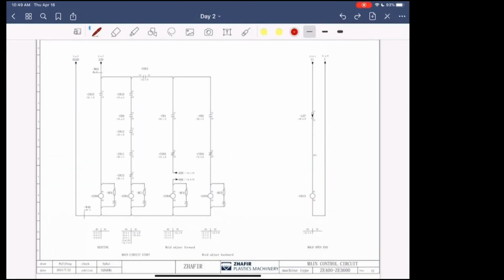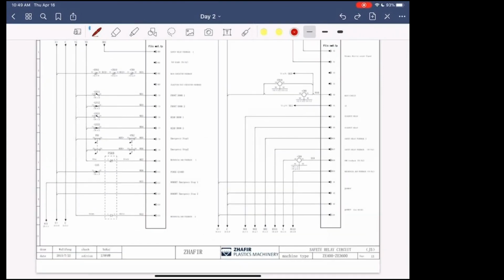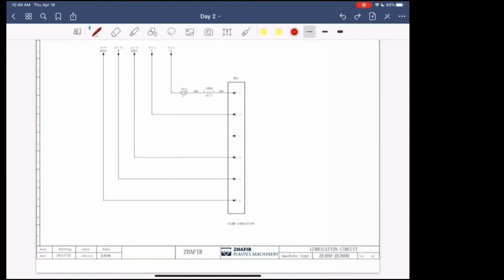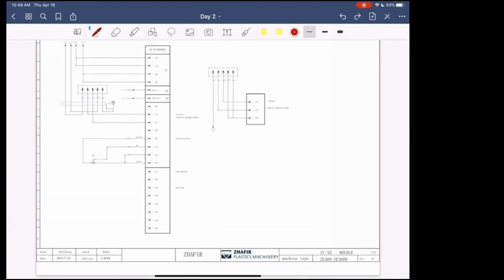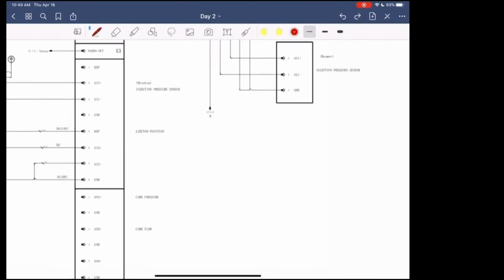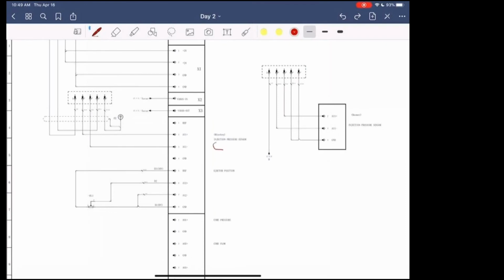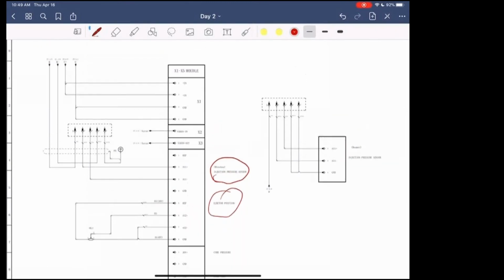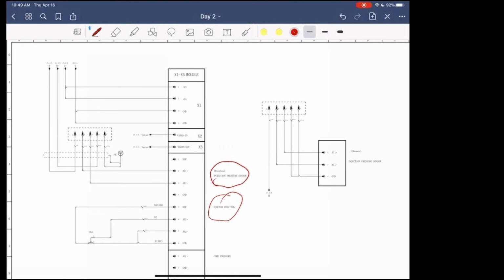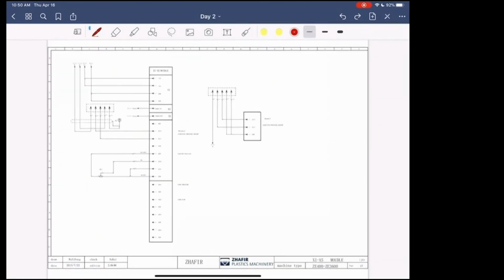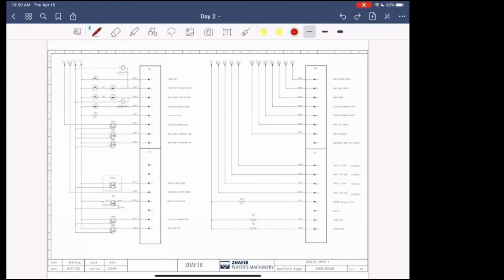So on the KEB drive itself, it's going to have a J5 card. Here it is. So what this does is it checks the injection pressure sensor, the ejector position, etc. But it also has inputs for the injection pressure, the sensor for the ejectors, etc. It's not on here. They're calling it injection pressure sensor, but it's actually a sensor for the system itself. I believe they put injection pressure sensor because they're assuming it's a Mars machine. They didn't want to change the prints or something.